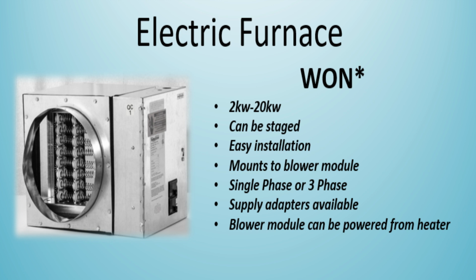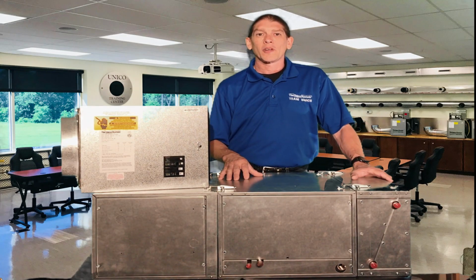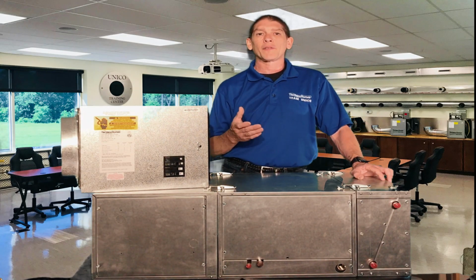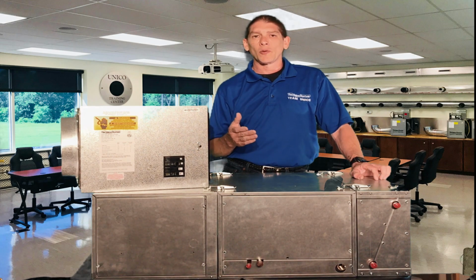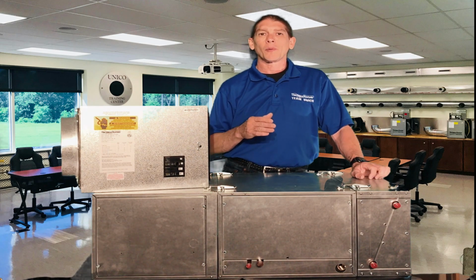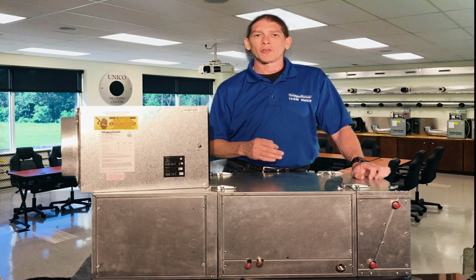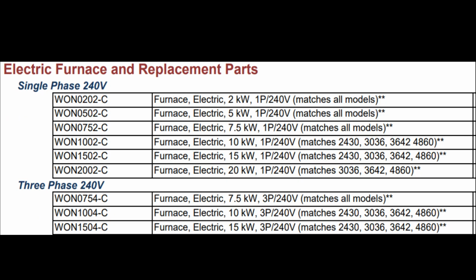We have a wide range of electric heaters, 2, 5, 7.5, 10, 15, and 20 kilowatts. Most can be staged. For example, the 10 kilowatt can be staged for 5 kilowatts for the first stage and then 10 kilowatts for the second stage. Depending on the blower size, you may be limited on the size of heater to be used. For example, the M1218 can be used in conjunction with the 2, 5, and 7.5 kilowatts, where the M3036, however, can be matched to any size. Refer to the installation manuals or current price book for proper sizing.